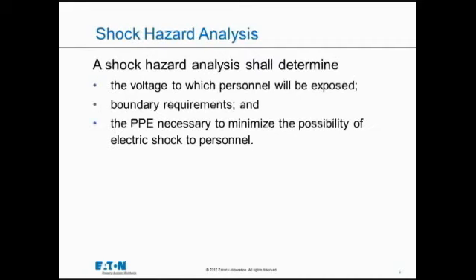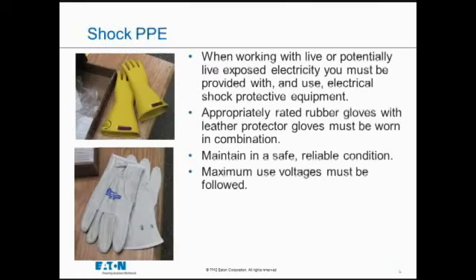And this is an example just showing some rubber gloves and leather protectors. And still to this day, last year we had one of our field service persons tell us they were out at a customer site in the Toronto area and they were putting the rubber gloves over top of the leather gloves. Opposite to what you should be doing, but that's an unusual case. People just didn't know. You got 2 pairs of gloves, which way do we put them on? They had the wrong way. Didn't have the rubber on the inside.